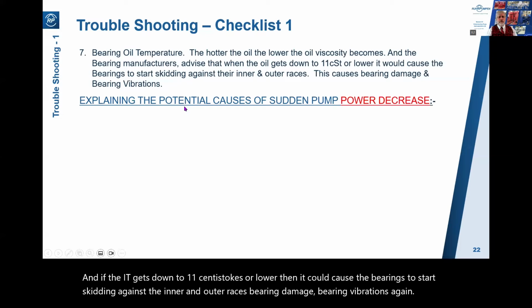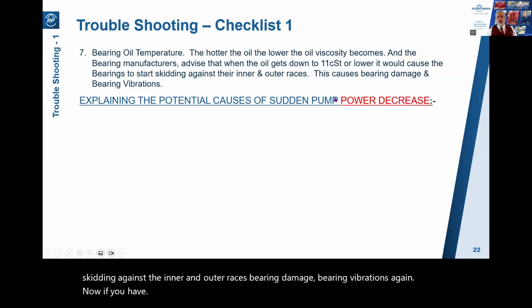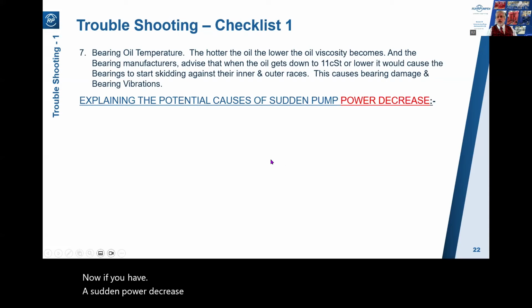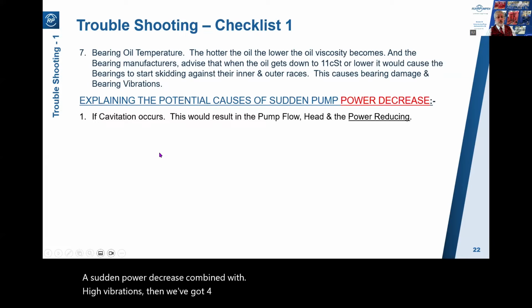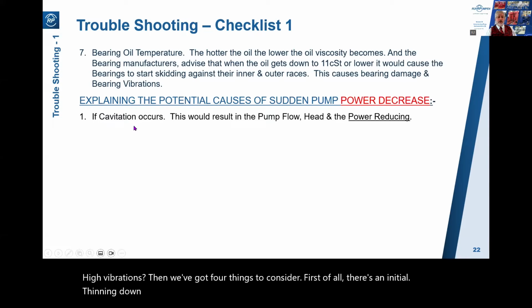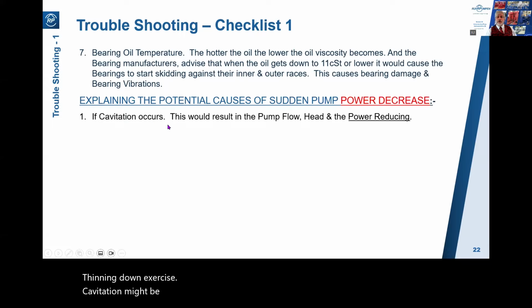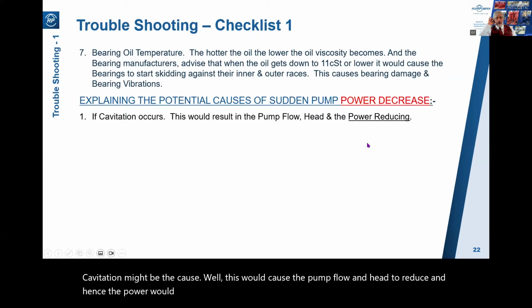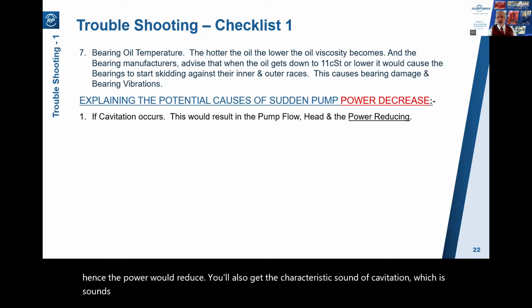Now, if you have a sudden power decrease combined with high vibrations, then we've got 4 things to consider. First of all, as an initial thinning down exercise, cavitation might be the cause. This would cause the pump flow and head to reduce, and hence the power would reduce. You'll also get the characteristic sound of cavitation, which sounds like someone's taken a handful of gravel and thrown it in your pump.